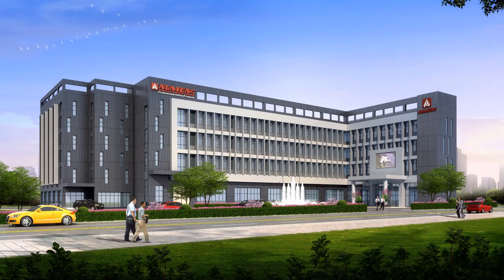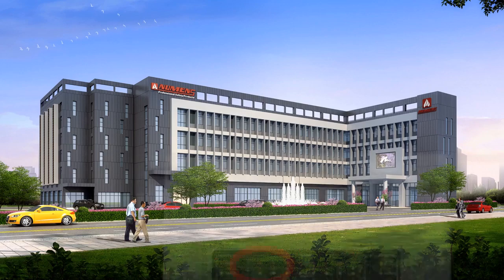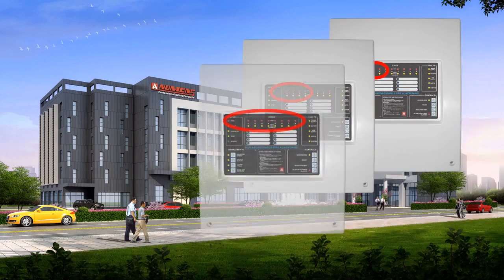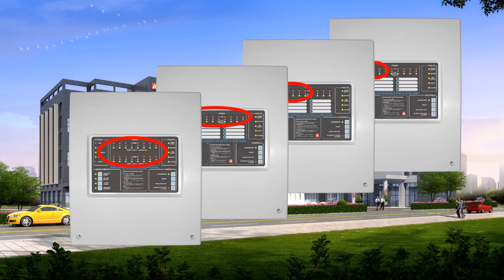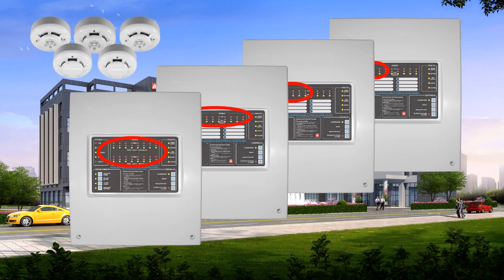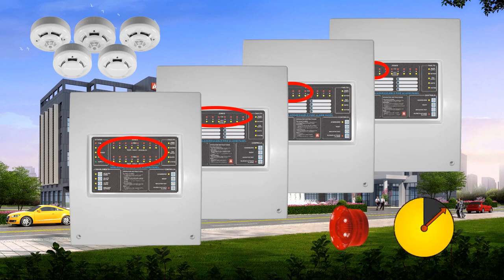The 4001 is a non-addressable panel with features that provide a flexible solution for small and medium-sized buildings. The panel comes with 2, 4, 8 or 16 detection zones. Each detection zone supports up to 32 non-addressable detectors. The detection zones can be configured for non-latching operation or alarm dependency. We'll show how this is done later. A configurable alarm delay timer can be set to pause before the audio-visual alarm devices operate. We'll also cover this configuration later.